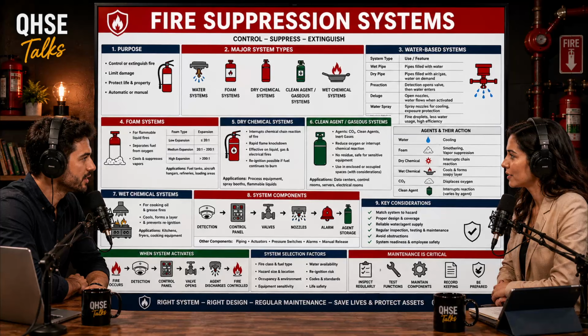Because the pipes will freeze and burst. Right. And when the ice eventually thaws, the municipal water supply just pumps thousands of gallons of water through the broken pipes, destroying the facility. Which naturally leads us to the engineering solution for freezing environments: the dry pipe system. Explain the mechanics of this, because it's more complex than just emptying the pipes.